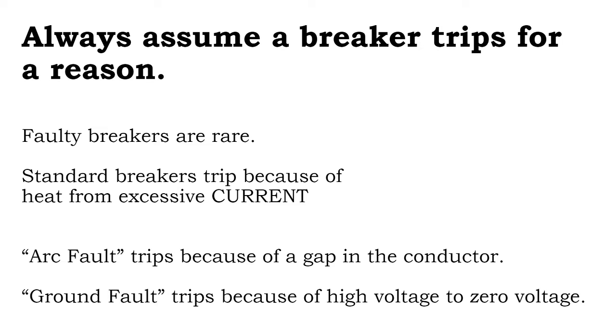And so in my experience, the breakers trip for a reason. It's not that it's a faulty breaker, it's that there's something real with the electricity that is physical, that is going on, that's causing the breaker to trip. It's not like an electronic glitch. And the mechanical failure of the breaker is rare.